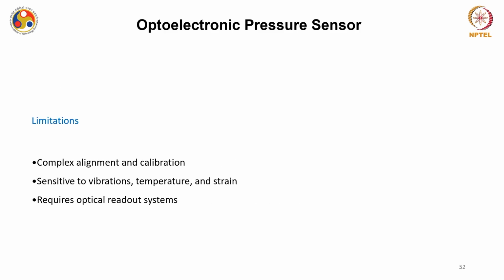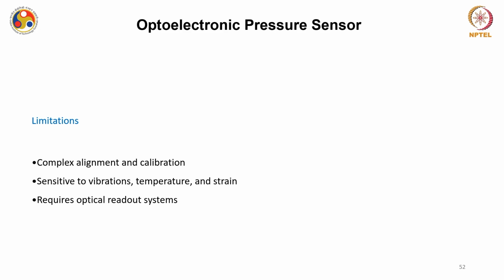However, not everything is good about these optoelectronic pressure sensors. There are certain limitations associated with them. Since you have seen that there are cavities, half mirrors, and then perfect mirrors placed in the configuration, that too in a silicon micromachined area, their alignments are very complex and the calibration is also very challenging. These devices, although not very susceptible to temperature change, still have variations with respect to temperature, strain as well as vibrations. And they require special skills in developing the readout systems for these optical systems.